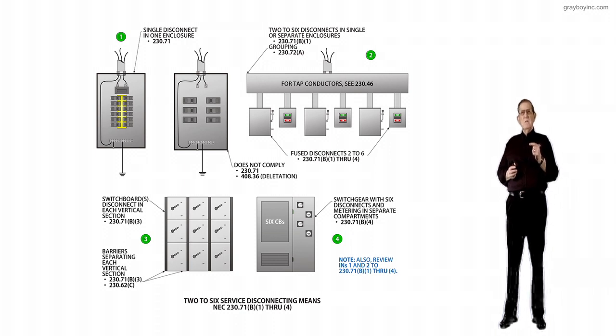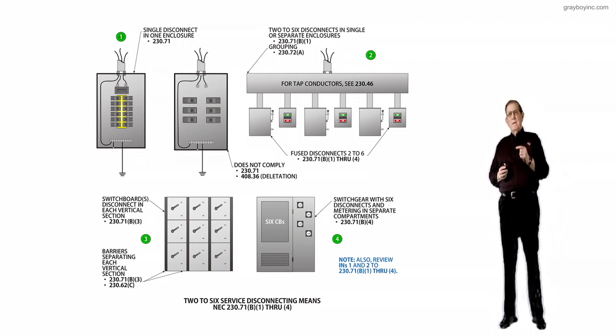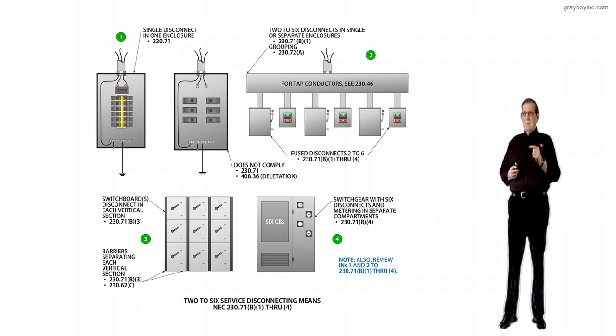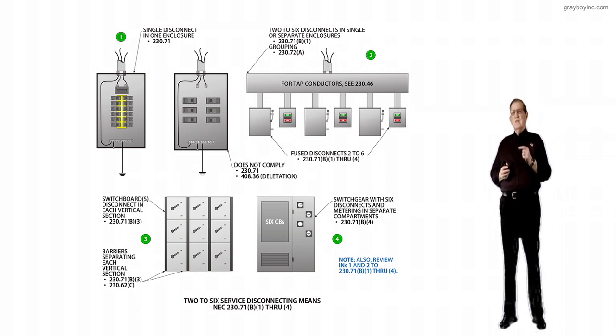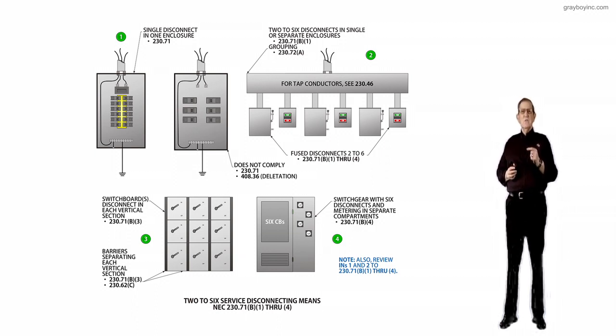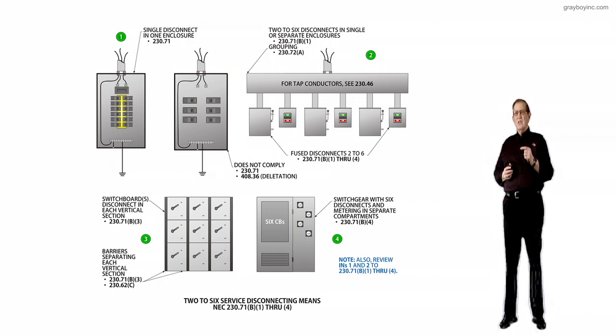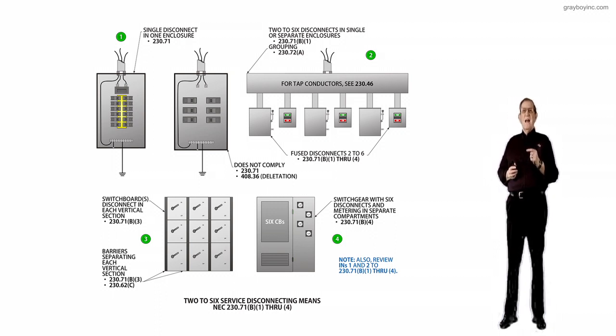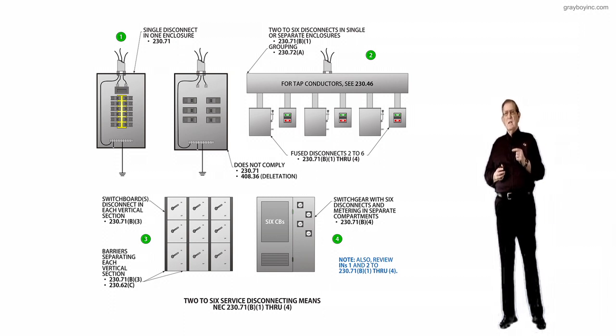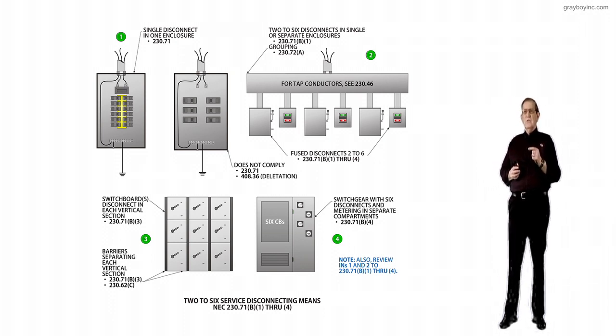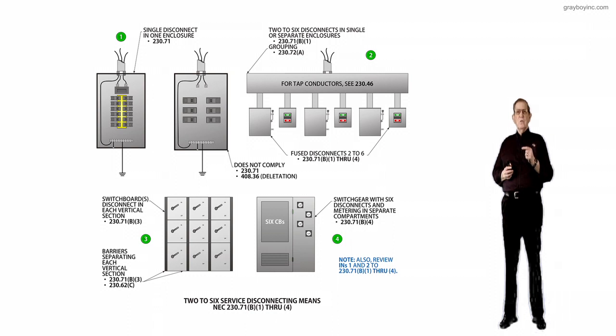This revision provides the ability of an installer and maintainer to operate a single disconnect that de-energizes conductors and circuit parts in the same enclosure, except for the line side of the disconnecting mains. This reduces the likelihood of an incident with energized conductors or circuit parts in the service equipment, enhancing safety.